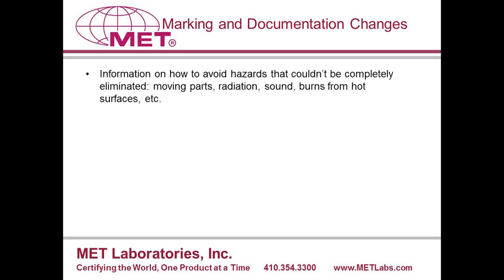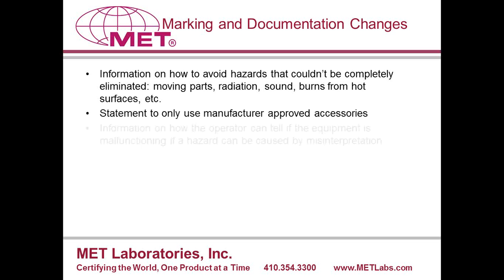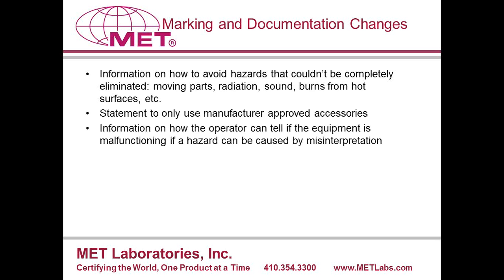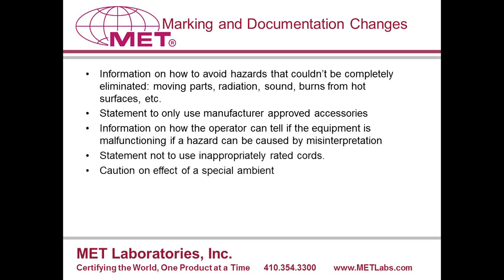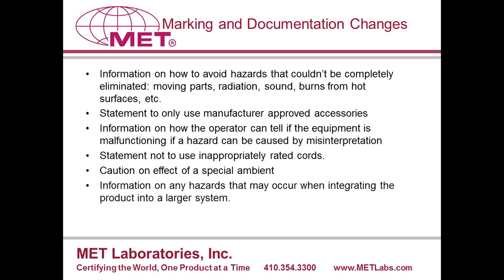Now, here are 6 new requirements to the user manual. You'll need to provide information on how to avoid a hazard that can't be eliminated in the design. You'll need a statement to only use manufacturer-approved accessories, such as probes. You'll need to provide information on how to tell if a measuring device, such as a hazardous gas sensor, is malfunctioning. You'll need a statement not to use inappropriately rated power cords. You'll need information on any hazards from putting the product into an unusual environment, such as a wet or damp location, high humidity, or a toxic environment. And you'll need information on any hazards that may occur when the equipment is integrated into a larger system.